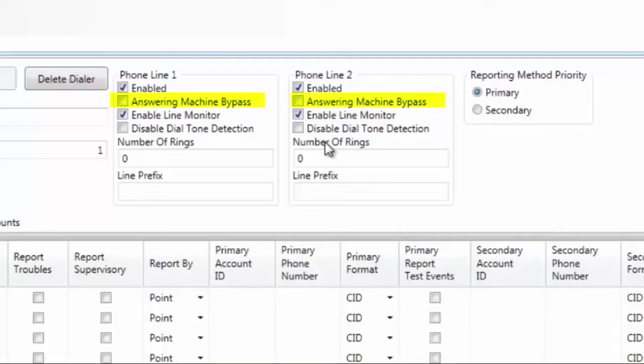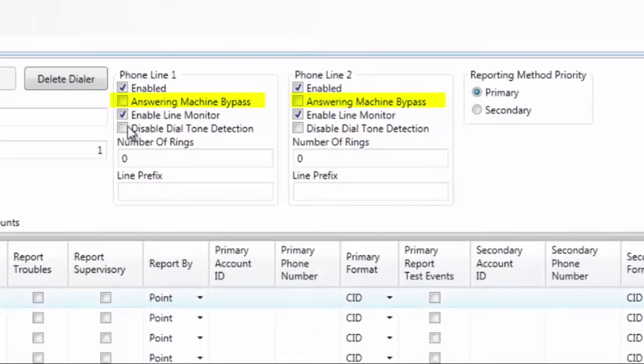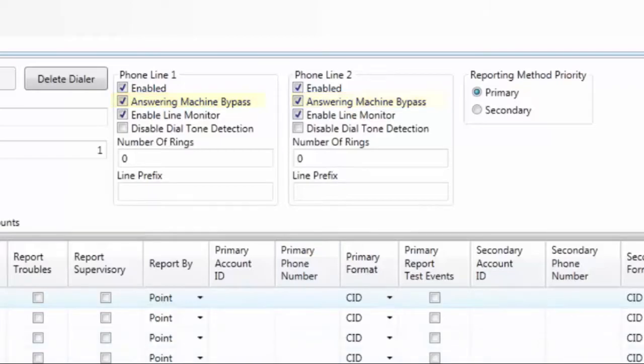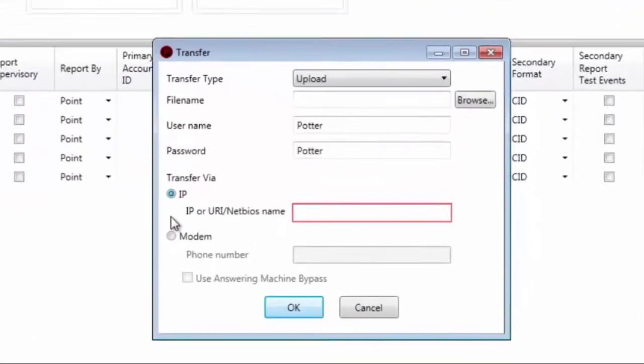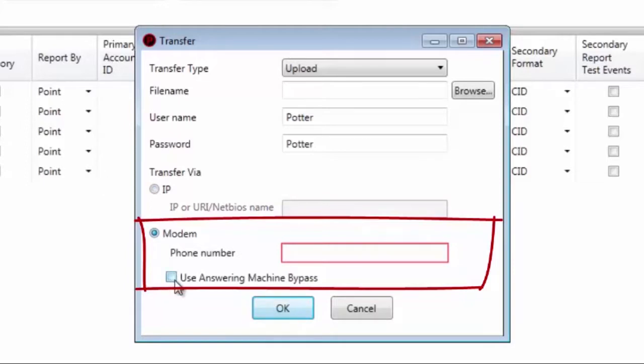Your next option is Answering Machine Bypass. The default for this is Unchecked. If the phone line is going to be shared with an Answering Machine or other device and remote access via that phone line is required, by checking the box, the UD1000 will answer the call in Answering Machine Bypass mode. Remember when accessing the panel remotely via a modem to check the Use Answering Machine Bypass box.